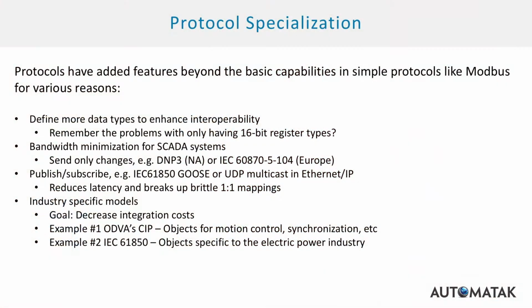Another reason that things have specialized, and this is more on the DCS side, is using publish-subscribe architectures. So if you're in a DCS, a lot of the protocols there will be these very chatty UDP multicast type protocols where they're constantly sending out their values to a group of subscribers. And in the DCS, where you're on a local area network, you're much less concerned about bandwidth than you would be in SCADA, so you can afford to constantly broadcast to your subscriber group all the things that are happening within the process, all the values that are changing, et cetera, et cetera.